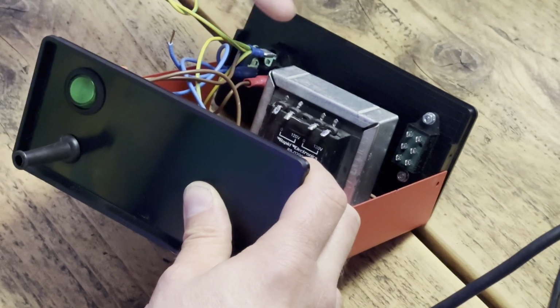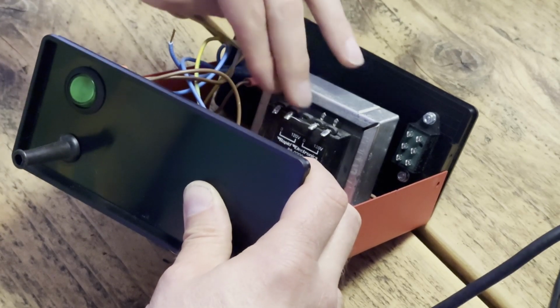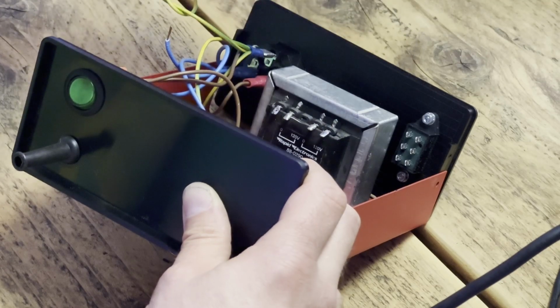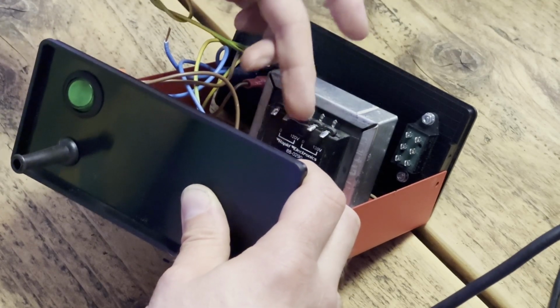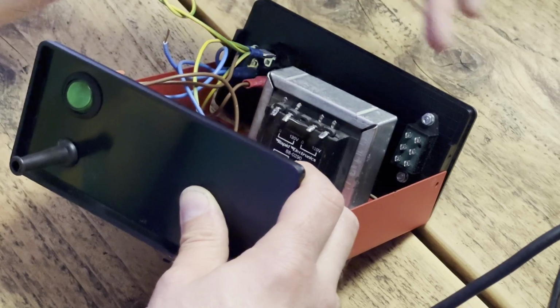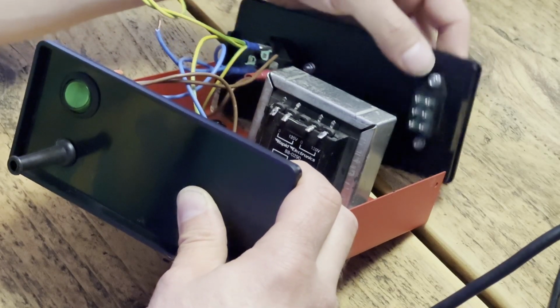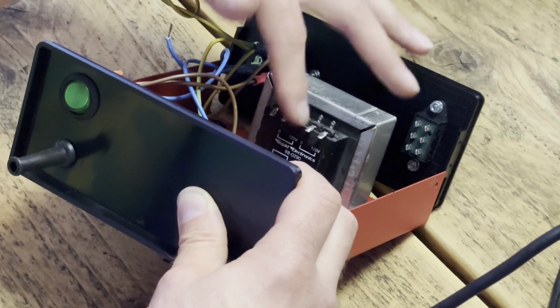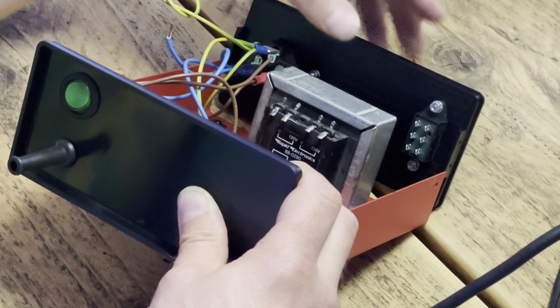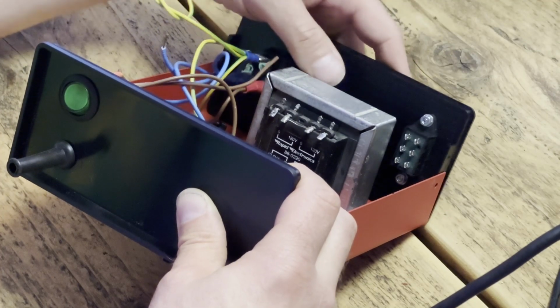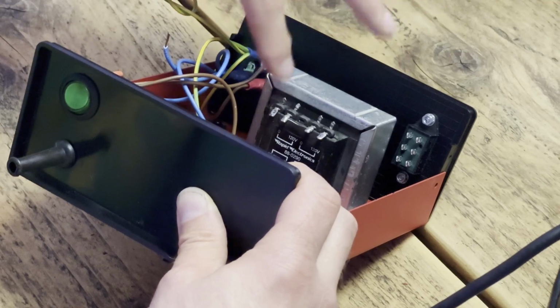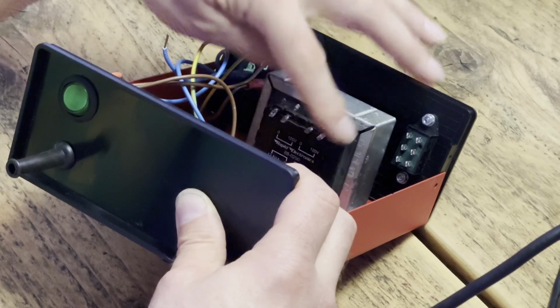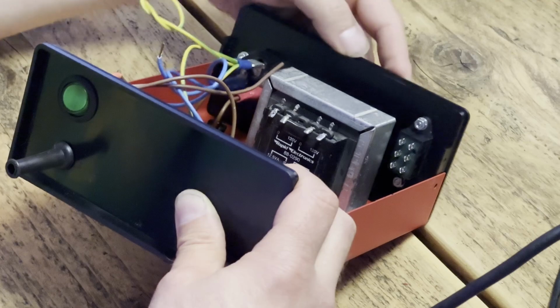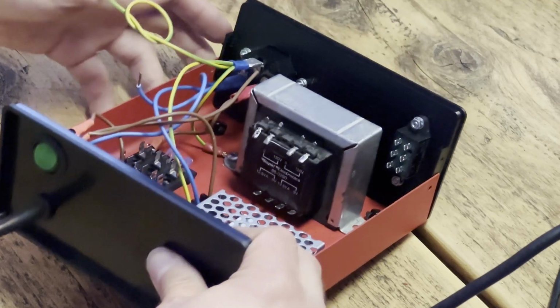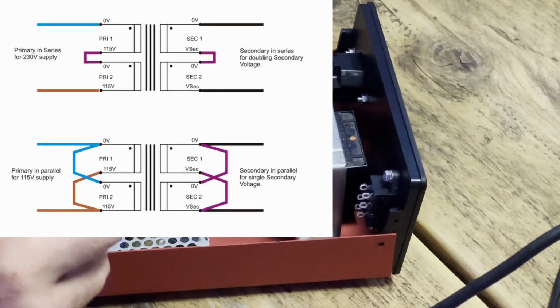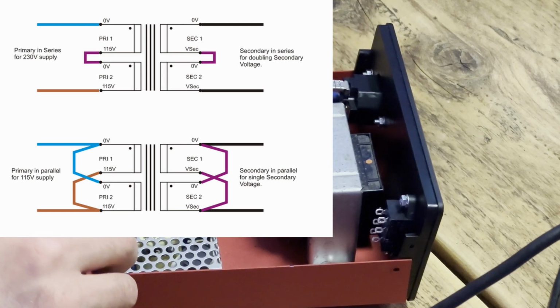But if you want to wire it for 110, 120 volts, you wire it in parallel. So what we need to do is cut this wire that someone's put in here, and then we can use this switch that we've installed on the back to switch it between 120 and 240 volts. Now, if you were doing this yourself, I would not bother with this at all. Just connect the wire in the middle, or just connect them in series or parallel, depending on what you want. I'll try and put a diagram up there to show you what to do.